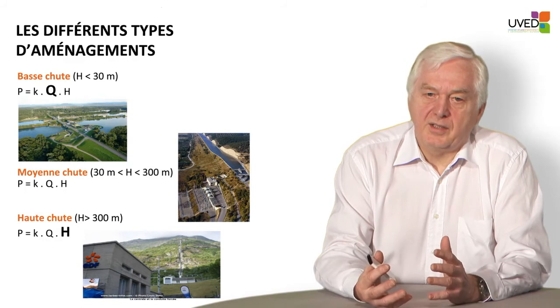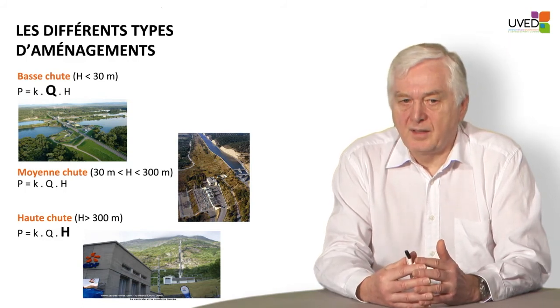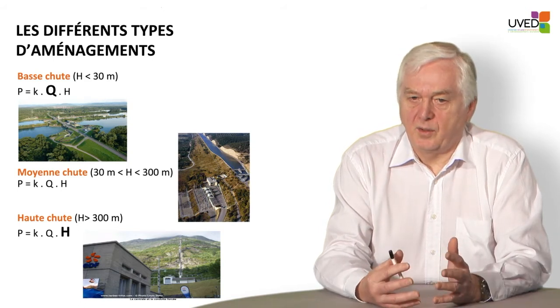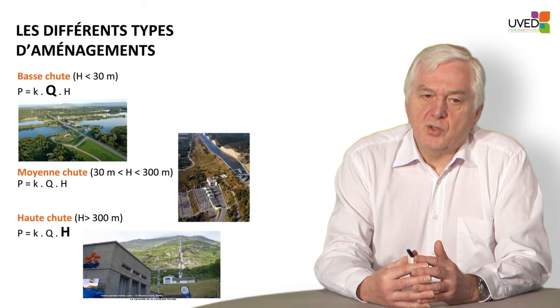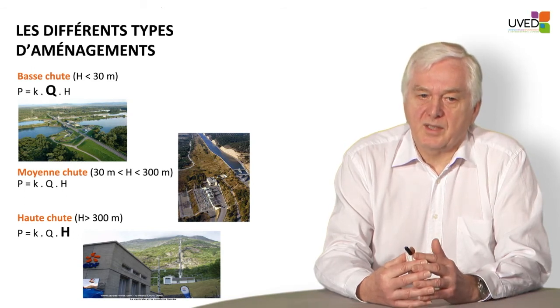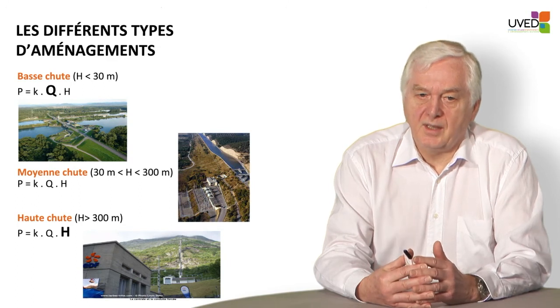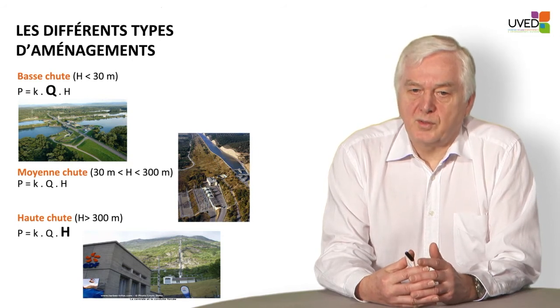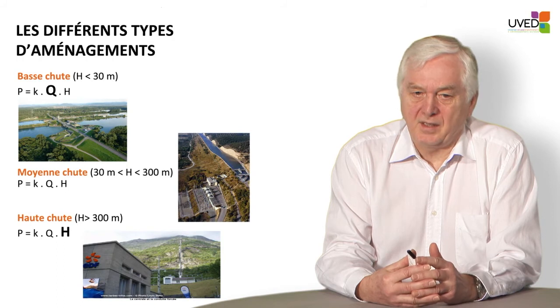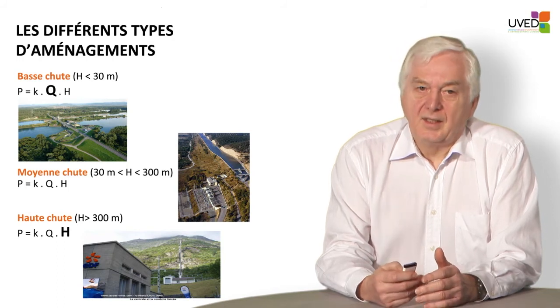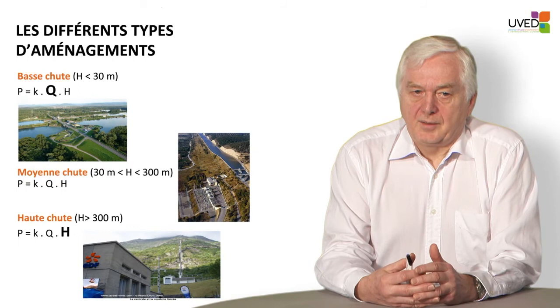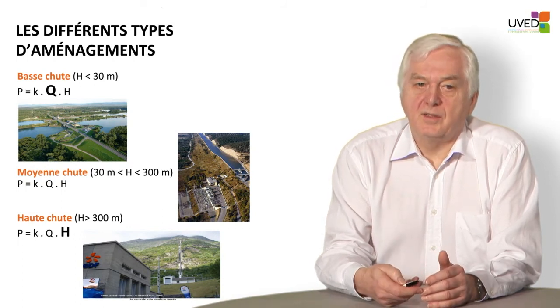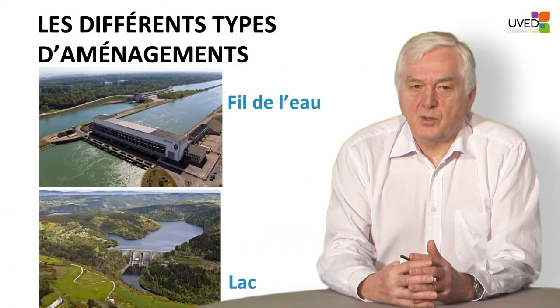Next, we have intermediate-head power plants when the head is between 30 and 300 meters. In order to achieve the same power, there are average flow and head values. High-head power plants are built when the head is in excess of 300 meters. Here we have a power plant in the Pyrenean mountains with almost 1,200 meters of head. You can see the penstock pipe coming from the top of the mountain right into the power plant. It is important to know these categories because the equipment differs enormously between the different types of heads.